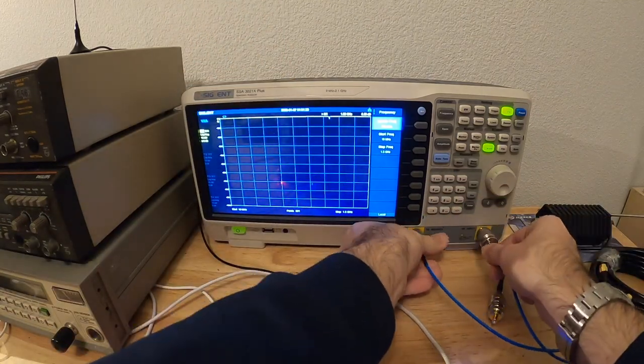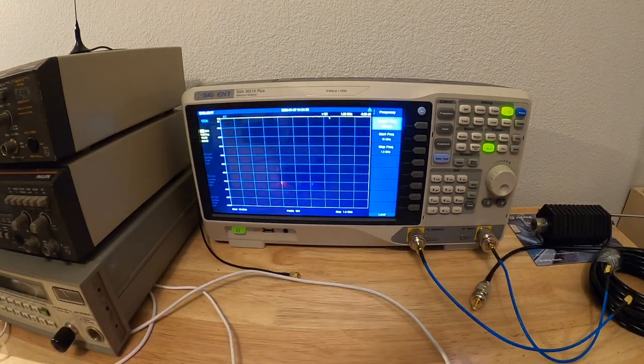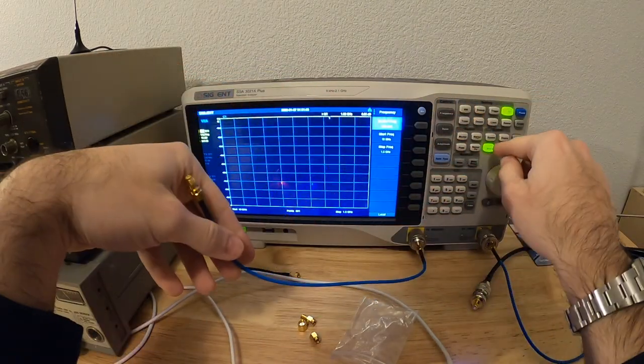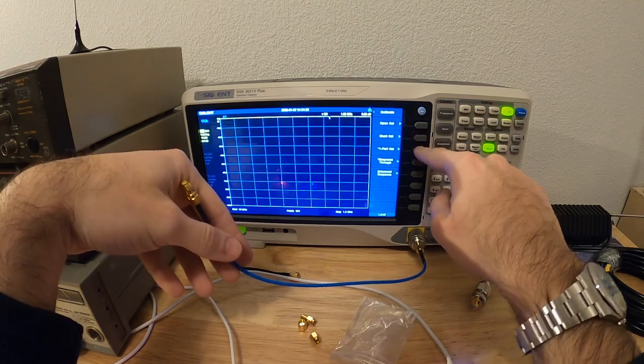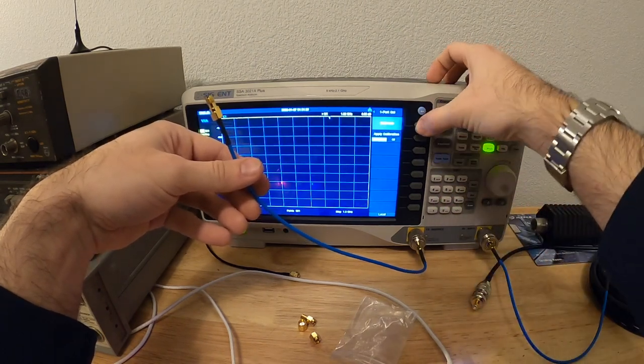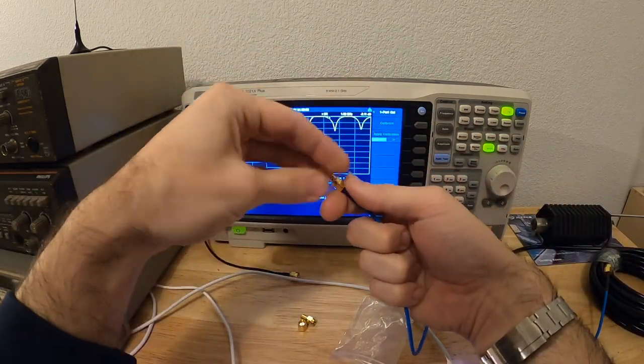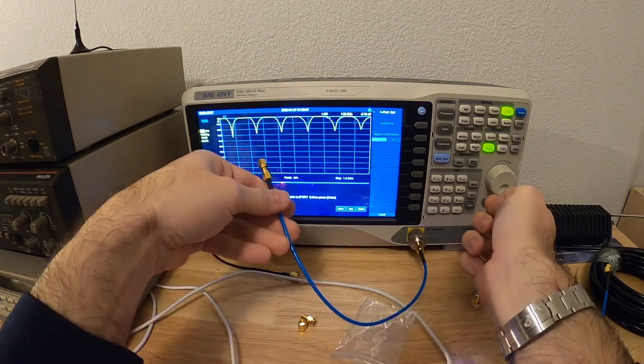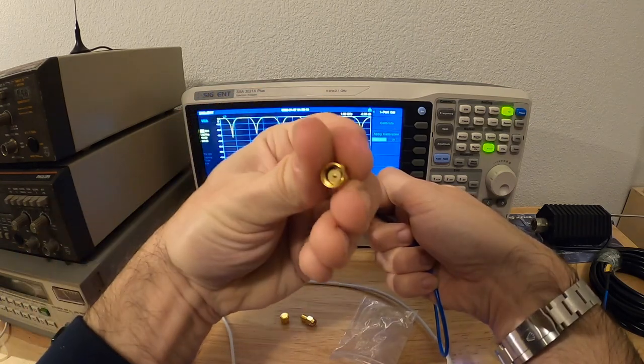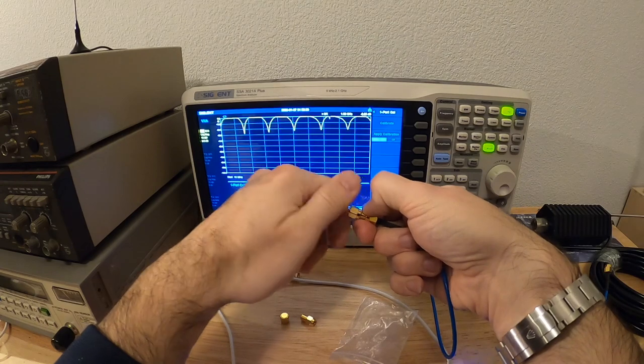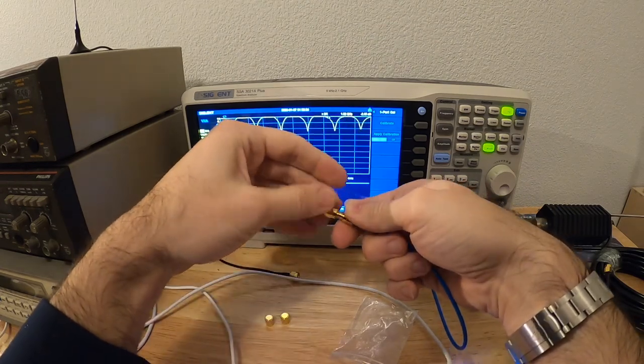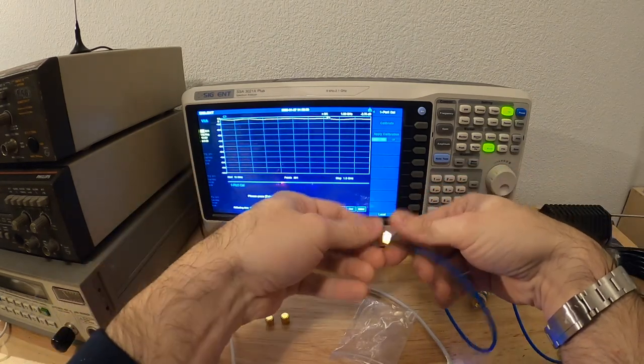So I just connect my two cables to my instrument, just like that. Then I take my calibration kit, put my adapter on the cable. And then I go into the instrument, VNA, calibration, calibrate, and I start to do the calibration of the first port. So one port calibration, and then I do calibrate. It's asking me for the open module, so the open module is the one with nothing inside. Just like that. And I do enter. Then it's asking me now for the short. So I'm putting the short module. That's pretty standard. Enter. Done. And finally, it's asking me for the load. Putting the load. Enter. And press enter to apply the calibration.